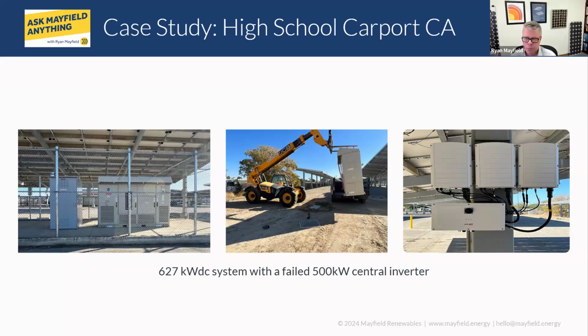We were within about plus or minus 10 to 12 percent. I think we were a little bit lucky, honestly. Those old SatCon inverters were putting out 200 volts AC, and that became a big sticking point, how are we going to do this. The client insisted on keeping the one SatCon that was still working, against both Cleanleaf's and Mayfield's recommendations. But being able to reuse a lot of the equipment took a lot of time and effort, figuring out the conduits, the conductors inside them, and how to make the system utilize as much existing infrastructure as possible.